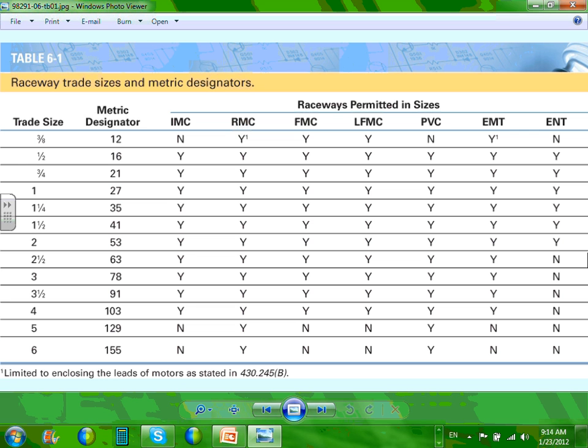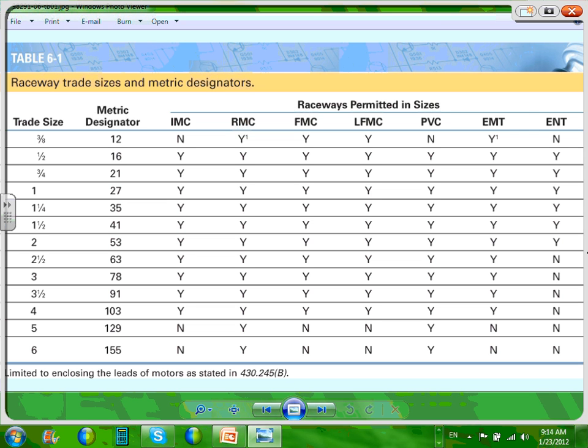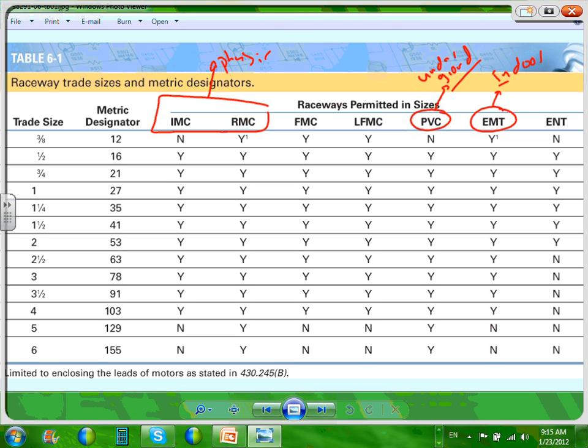Now conduits, as I told you, your option number 1 is EMT. And your option number 2 for underground is PVC. But then you have IMC and rigid. So I'm going to say this is indoor, this is underground. And the things that I highlight are the most important things about this conduit. Indoor, underground. These two conduits, intermediate and rigid, are for physical protection.